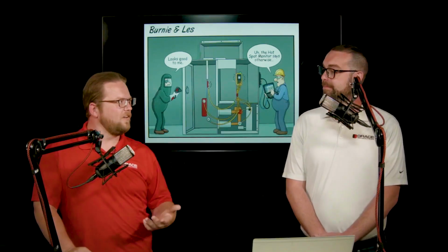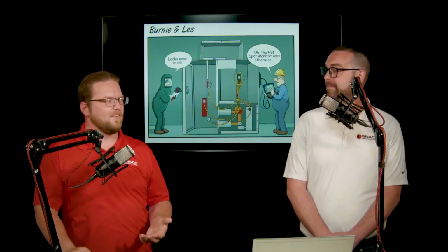Sure, but a lot of others are just called in. If you're the electrical contractor in the area and a hotel calls saying they're having power quality issues, you go out. I'm hearing stories about opening up power distribution equipment and finding 2 inches of dust inside, because no one's looked at it for years. There are 800 amp breakers just exploding out of panels.